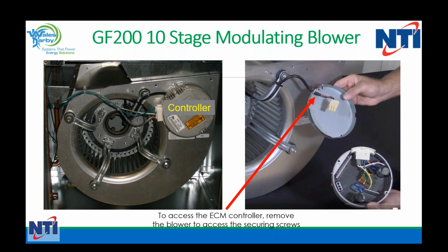So if you needed to work on this, remember, looking at the unit from the front, the right side door by the blower will come off, and you'll be looking right there at the controller. So just a reminder, if you're doing fresh air from the right side, return air from the right side, you have to be able to get to that controller.